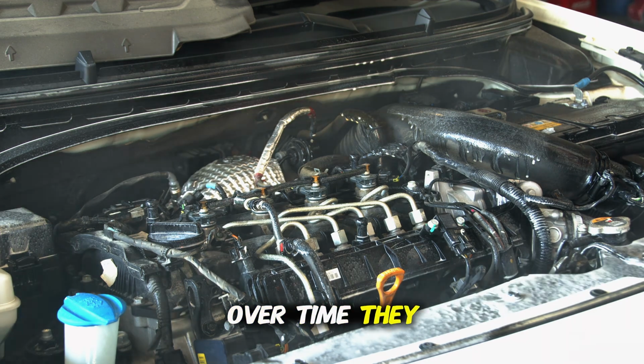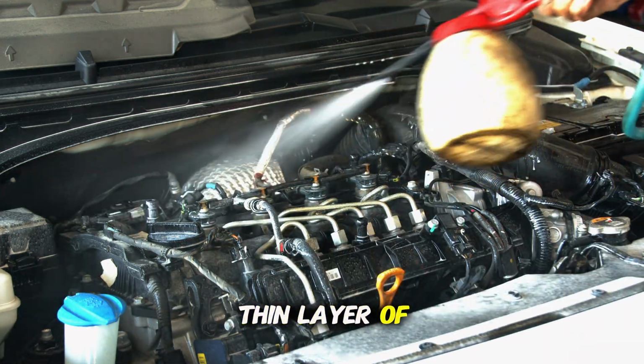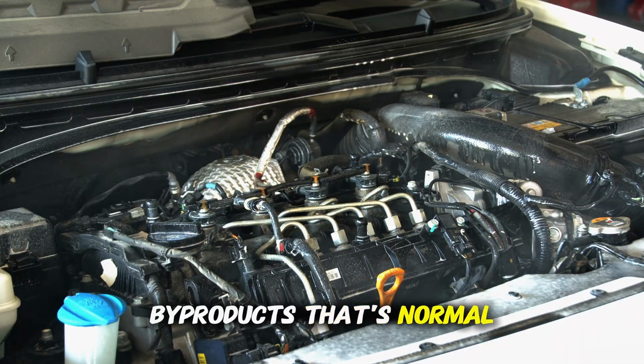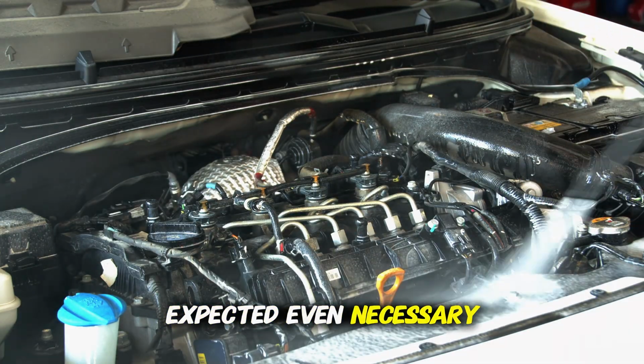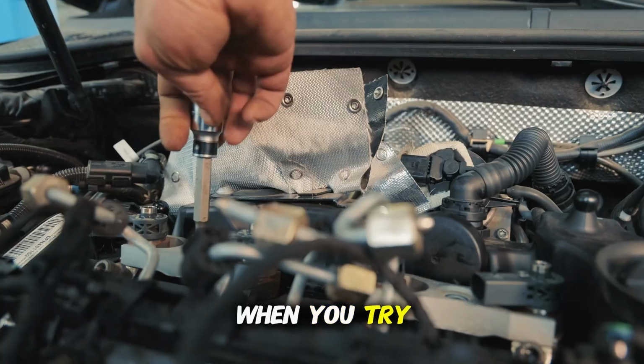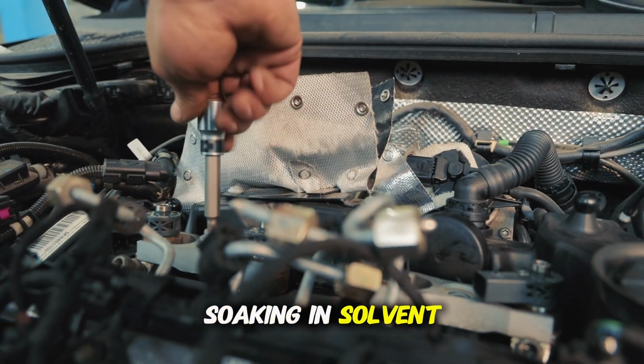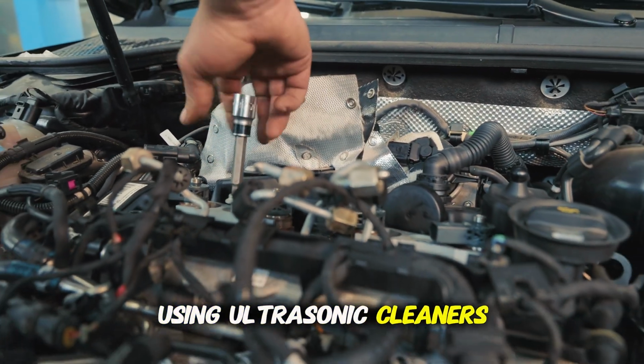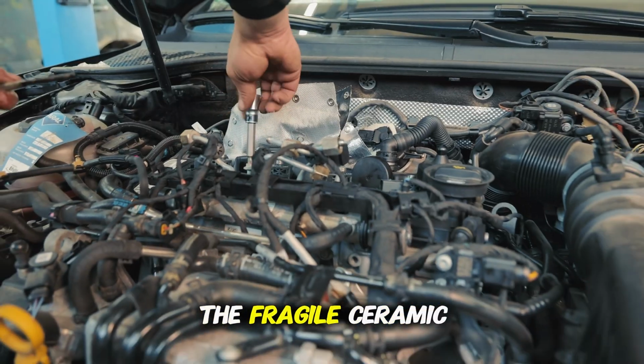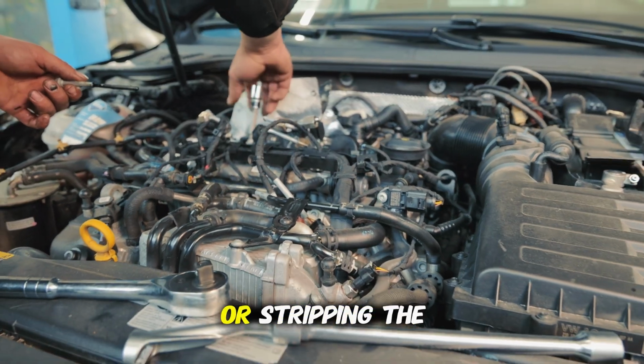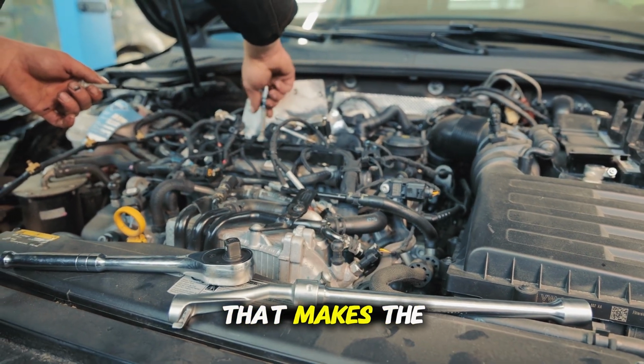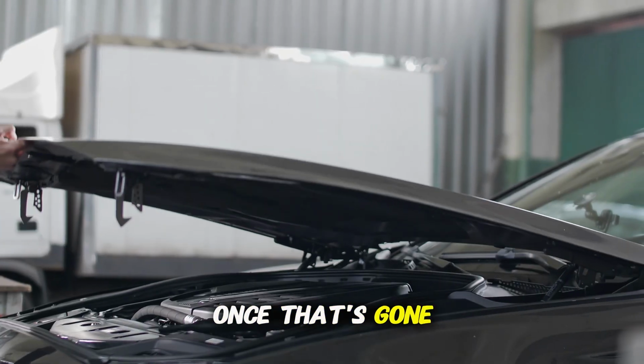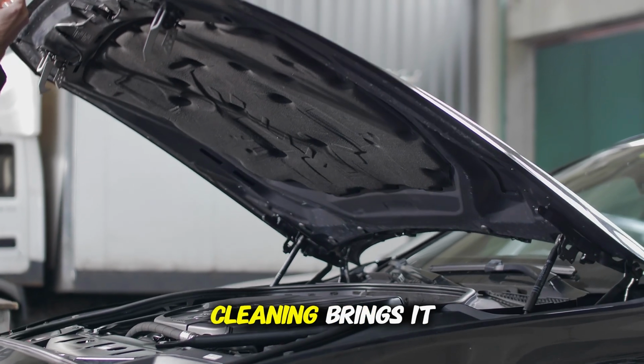Over time, they naturally accumulate a thin layer of combustion byproducts. That's normal, expected, even necessary for accurate readings. When you try to clean them, soaking in solvent, wire brushing, or using ultrasonic cleaners, you risk cracking the fragile ceramic element inside or stripping the zirconia coating that makes the sensor function. Once that's gone, it's dead. No amount of cleaning brings it back.